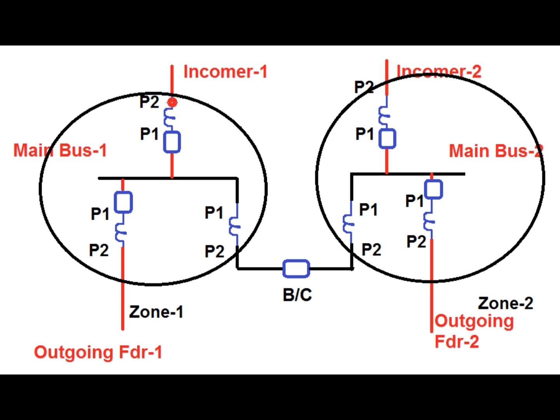Here P1 of all the CTs is connected towards the bus side, and P2 is connected towards the line side for the incomer and outgoing feeder. For the bus coupler CT, P2 is connected towards the bus coupler breaker. The CT shorting arrangement is such that S1 is shorted and the S2 terminal is taken to the bus bar relay. Since the protective object is the bus, CT shorting is done towards the protective object, which is the bus, and that is why S1 is shorted.